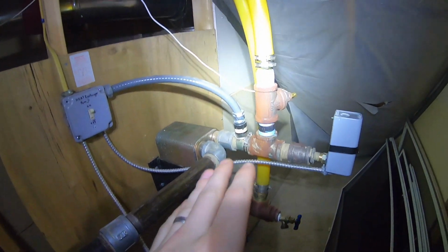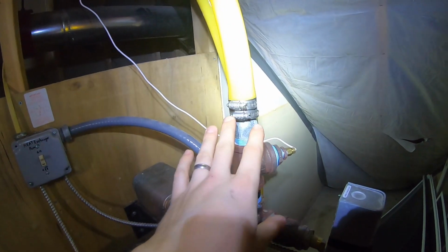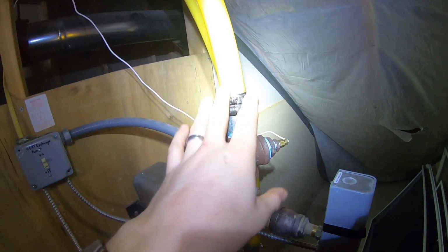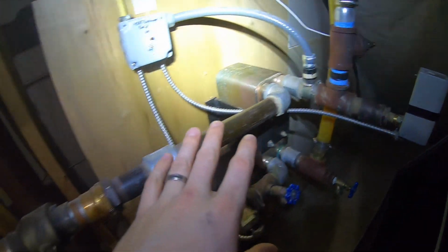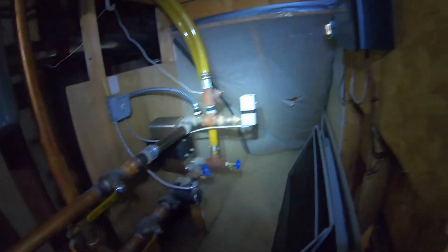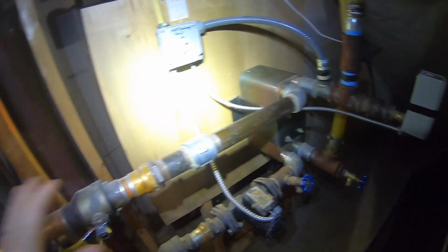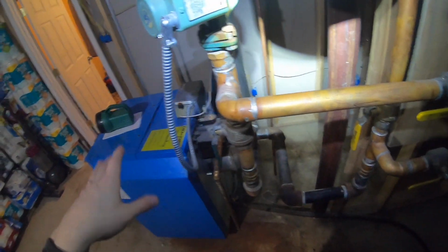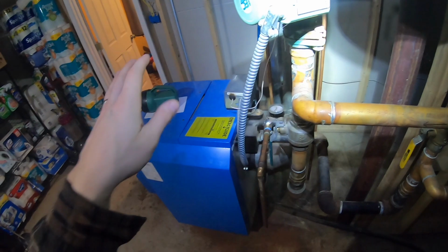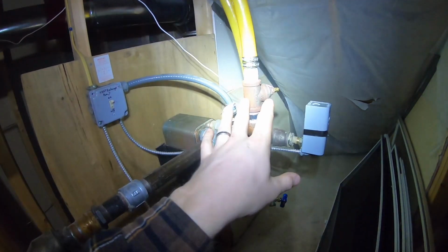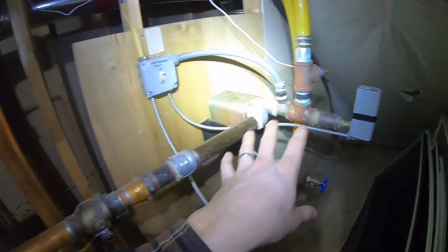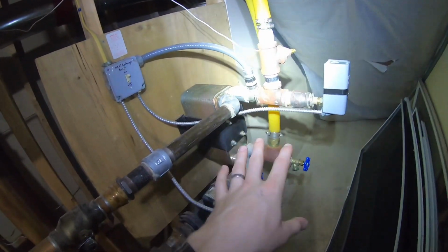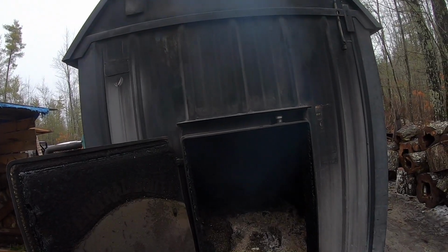One thing I want to point out is that this will not heat up the outdoor wood boiler water to 180 degrees again. It will only keep it at 130, enough to not freeze, and then obviously it needs to use other energy to continue to supply the heat for the other sides of the house. So it's pretty much a fail-safe. It'll keep the water at 130 degrees, and yes, it will still supply heat through the house. But basically, now you're relying on your oil furnace to maintain the 300-gallon water jacket at 130 degrees. So needless to say, it takes a fair amount of oil as a backup, if you're wondering.